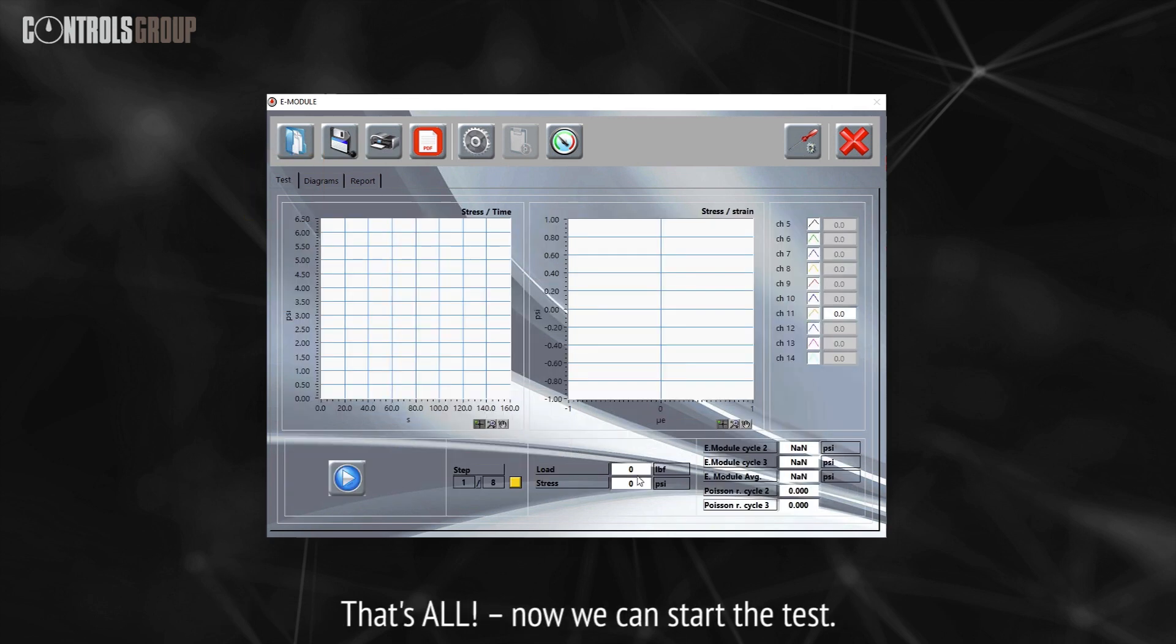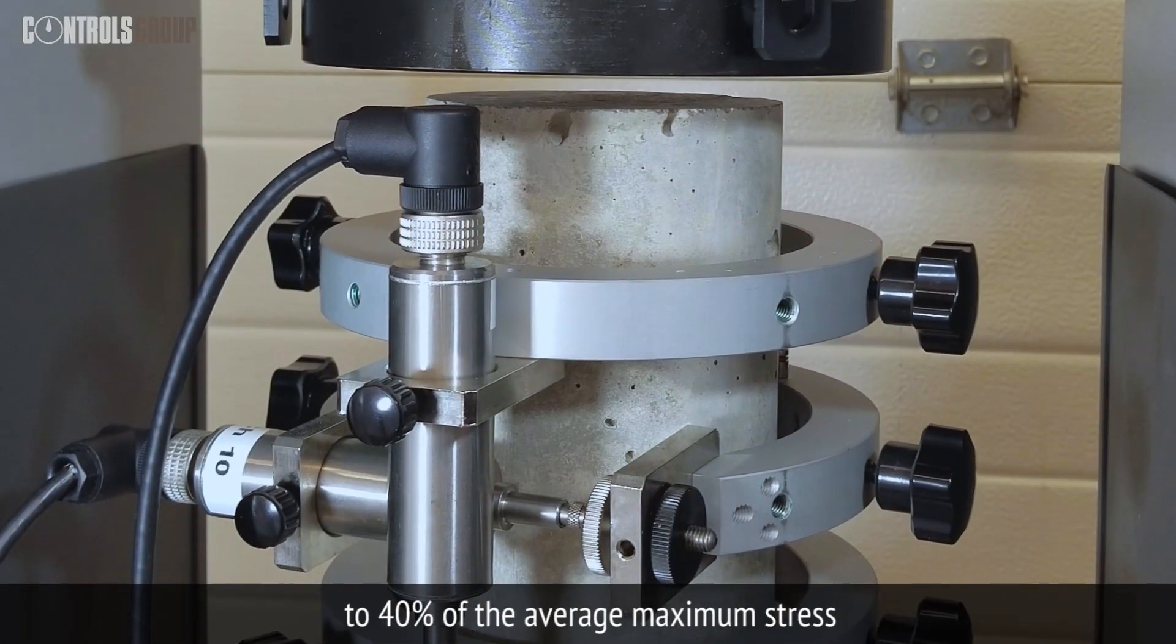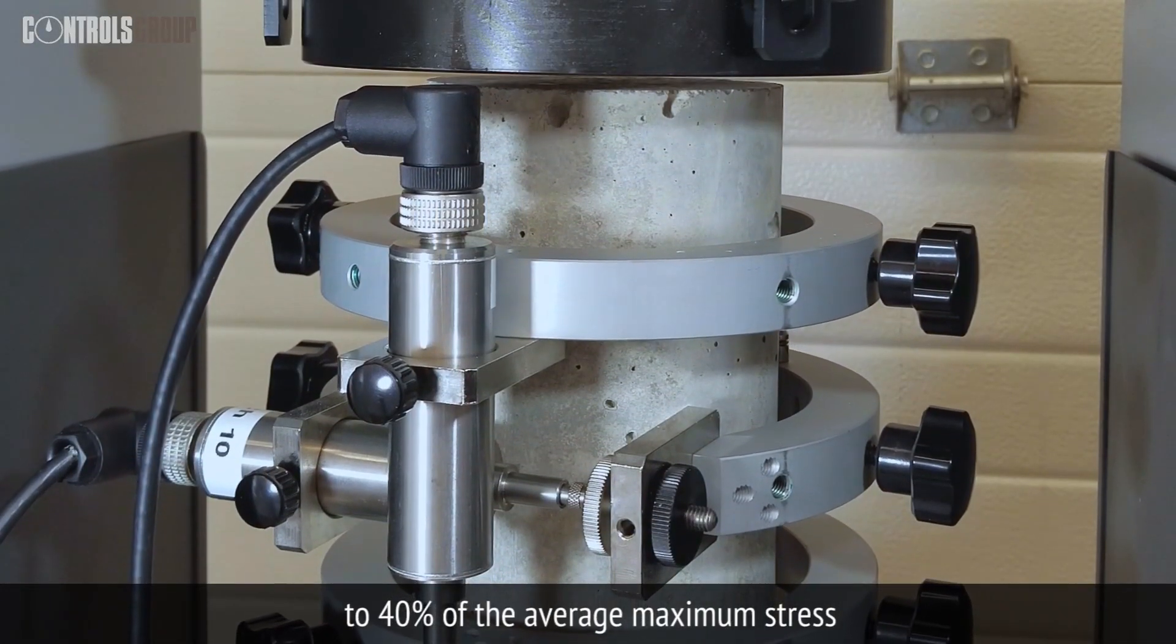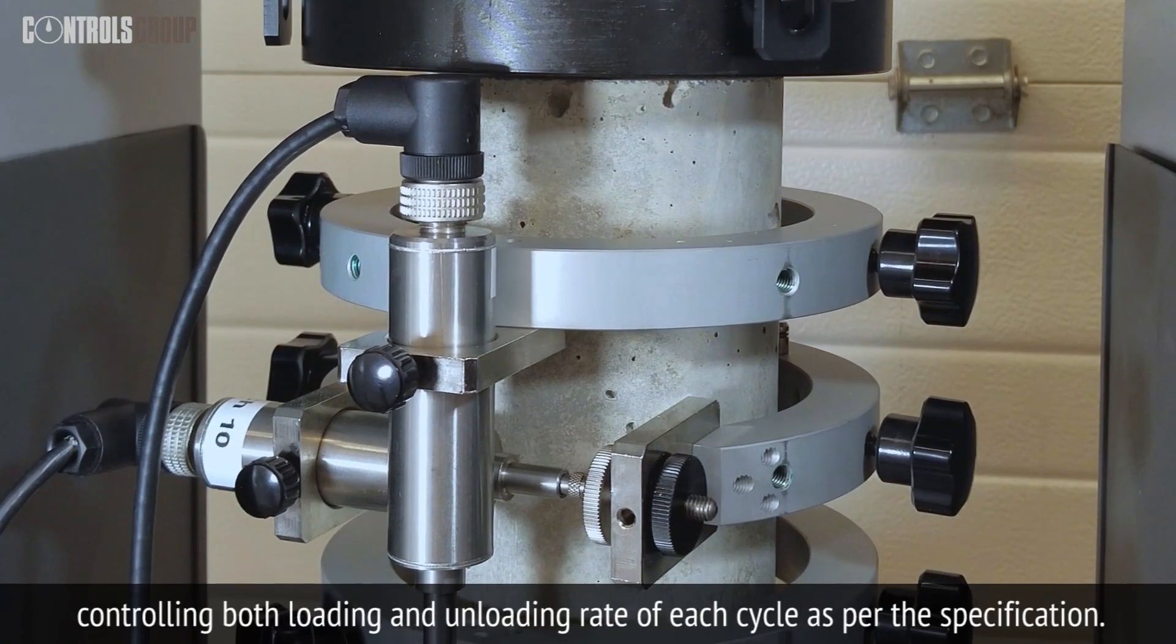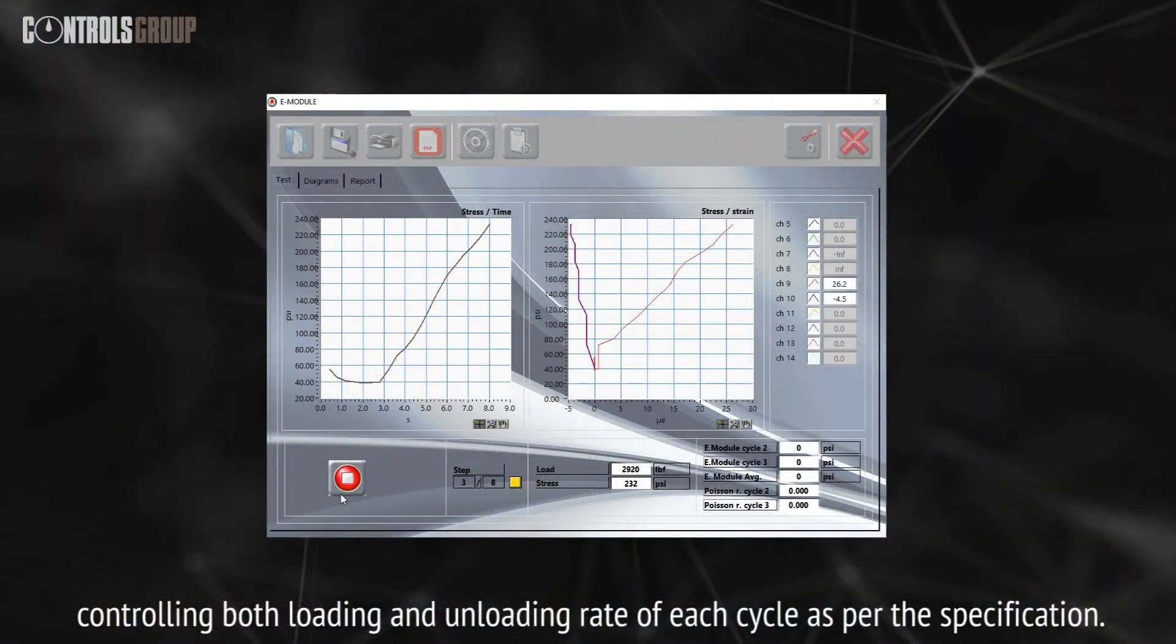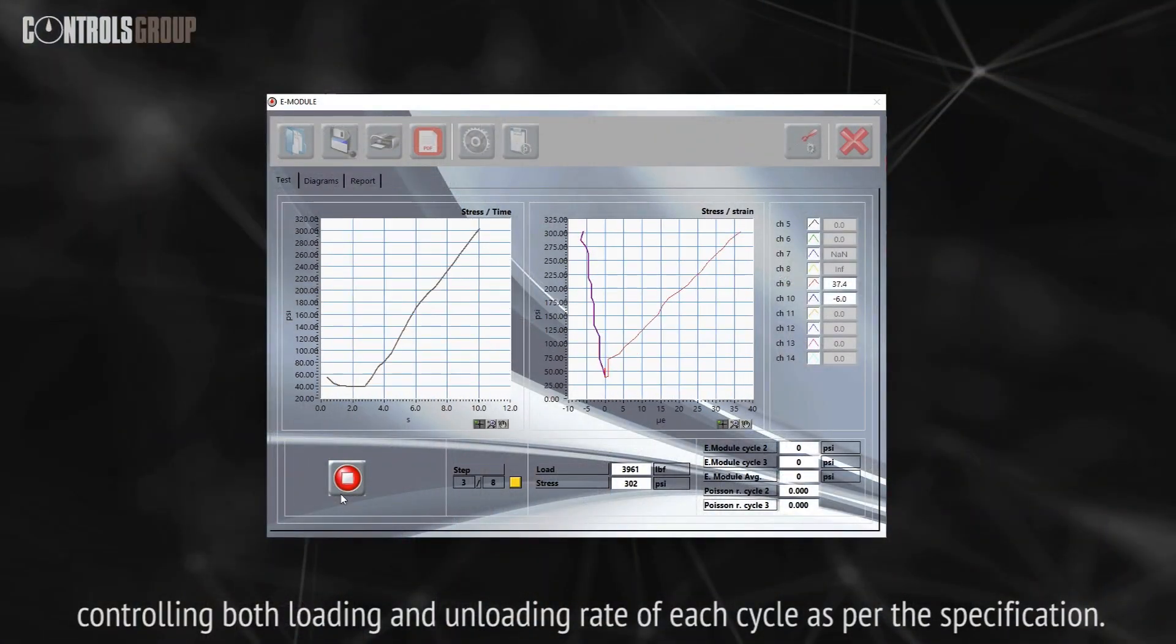Now we can start the test. AutoMax Multitest will load your cylinder three times to 40% of the average maximum stress, controlling both loading and unloading rate of each cycle as per the specification.